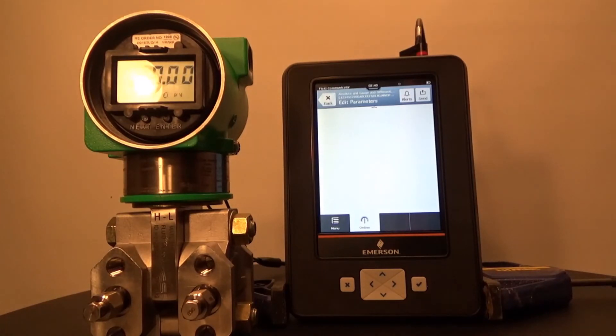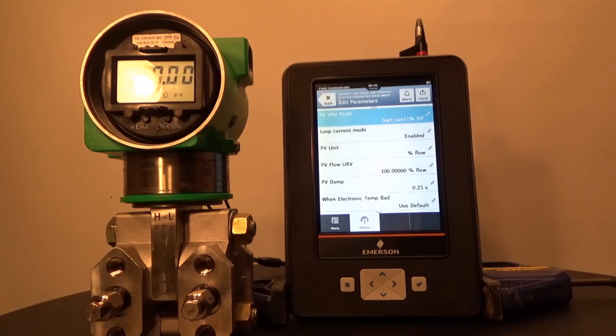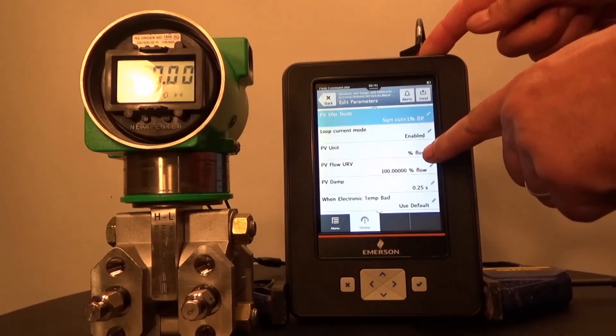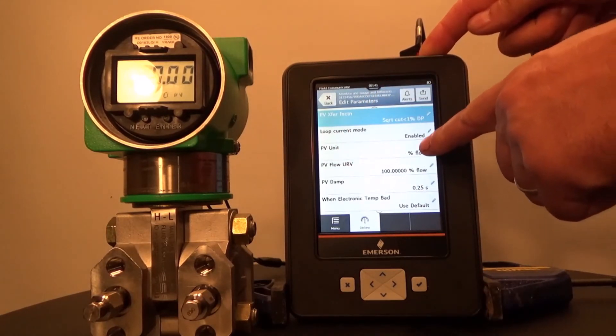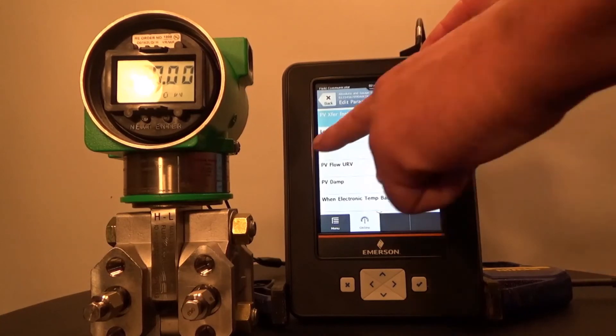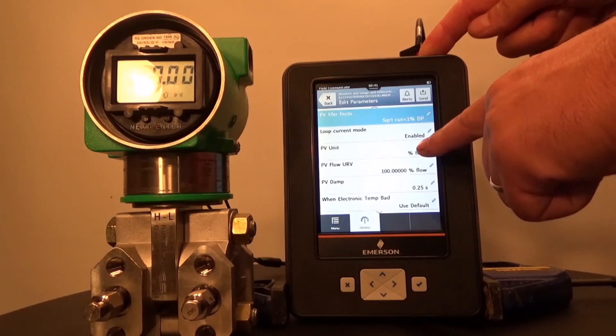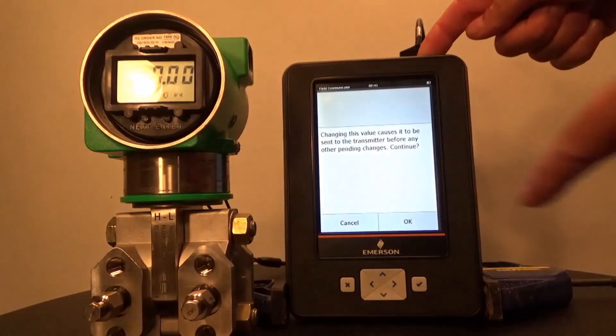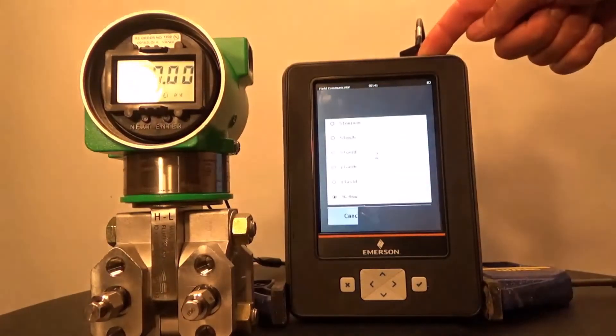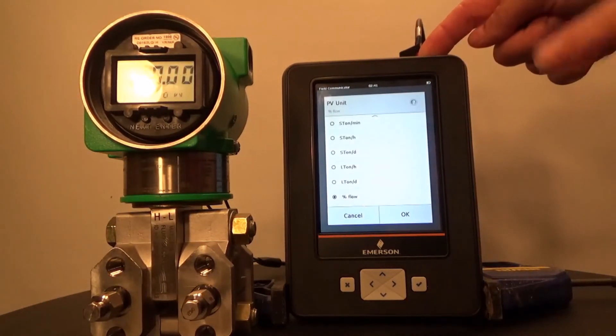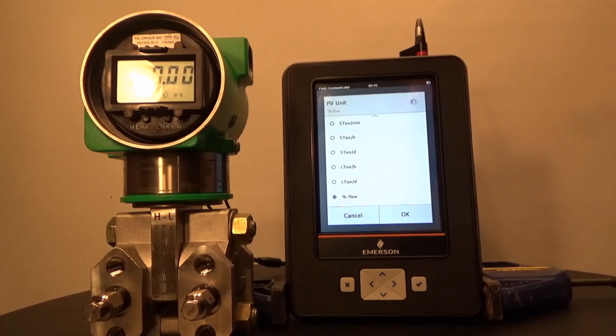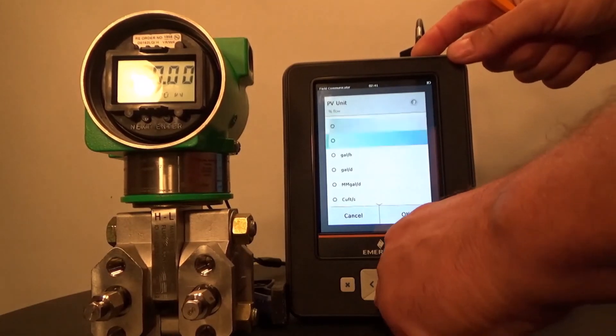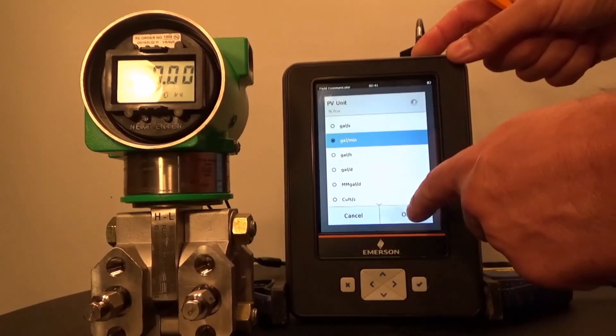That will be sent down to the transmitter and the TREX will return to the Edit Parameters screen. From the Edit Parameters screen, I'm now going to select PV Unit. Notice that because we changed the transfer function from linear to square root, these PV units automatically changed from inches of water to percent flow. I'm going to select PV Unit, say OK to the warning, and then select the required flow units for my application, which is gallons per minute, and press OK.